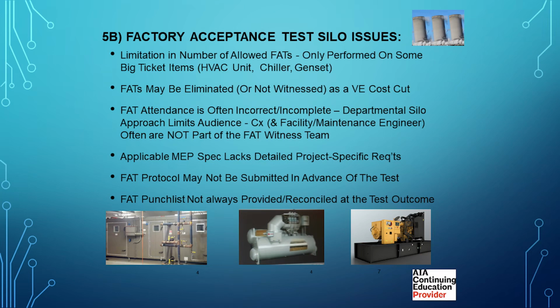Sometimes the factory acceptance test isn't done, or it's not witnessed, value engineered out. And if you're looking at the specification, the problem also is if the person writing it isn't aware of the requirements you need and how it fits into the owner's vision, he's not giving enough requirements in the contract language. So later on somebody says, well, I didn't have to do that in the FAT, and you're trying to argue, well, yes you should have, because maybe you know that from a previous job, or just in general how you test a UPS or an HVAC unit or FCU.